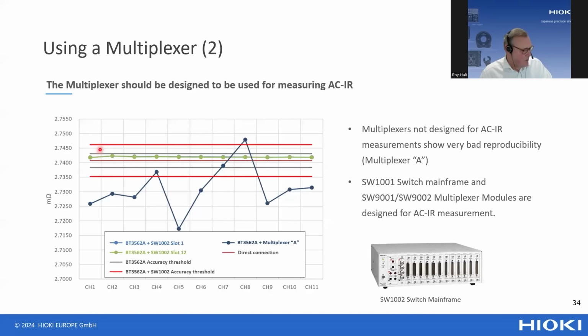After that, the switch connects to the same battery on all 11 channels. One input card has the capability to do 11 four-wire measurements, so we could connect 11 batteries to one input card, but for this test it was all measured on the same battery.